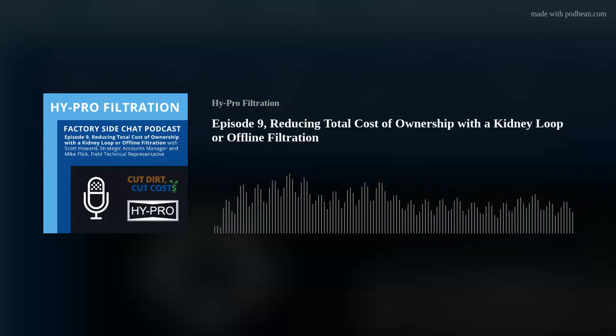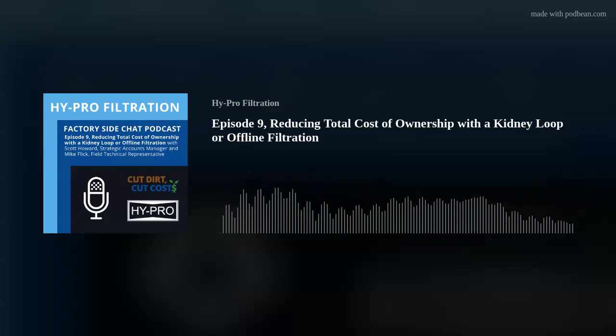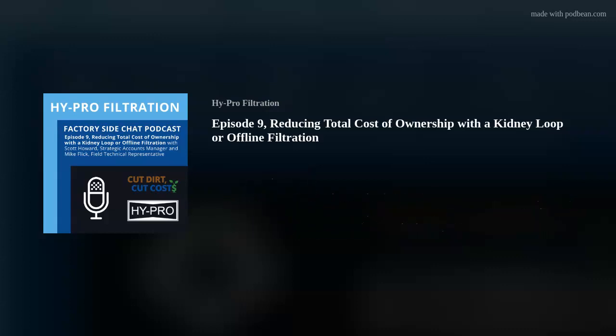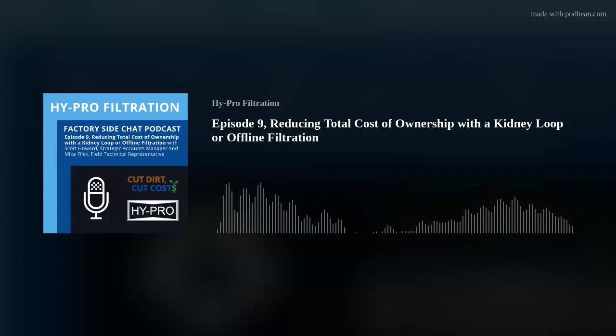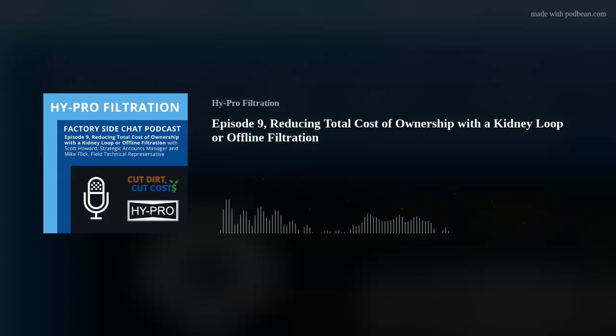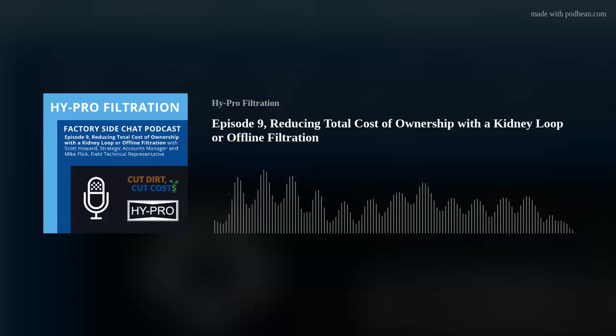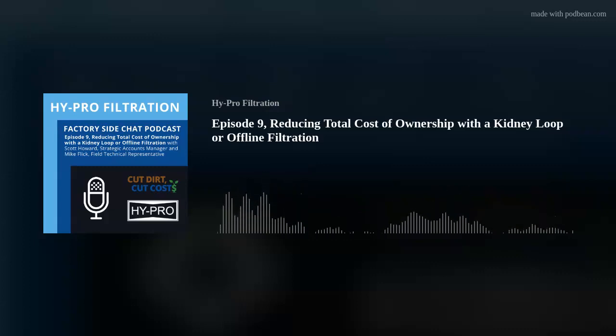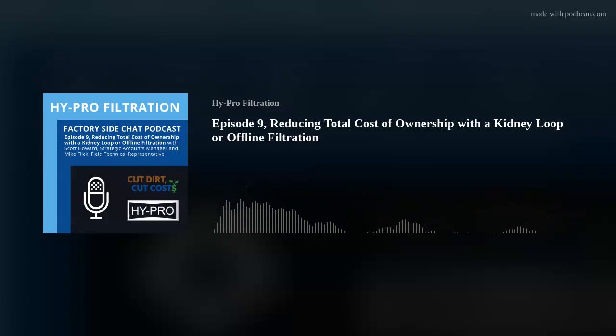And one of the things I'd like to start off with is when you go into a customer location and you feel the need to recommend a kidney loop or an offline filter unit, how does that conversation first go? Well, when I'm looking at a hydraulic system and their filtration needs, I always look and assess their current filtration system and see if they have pressure and return filters and proper filtration. And then the next thing we like to do is take a look at their ISO codes so we can make a determination on how clean or dirty their existing system is.